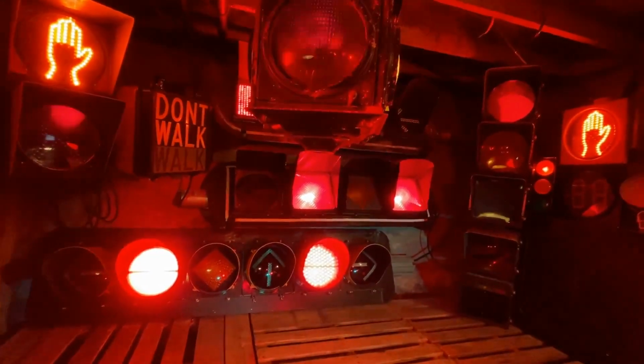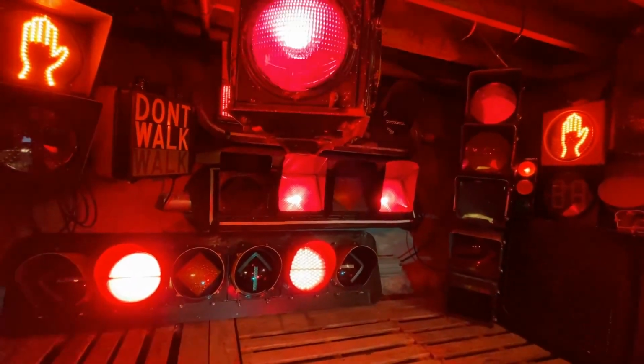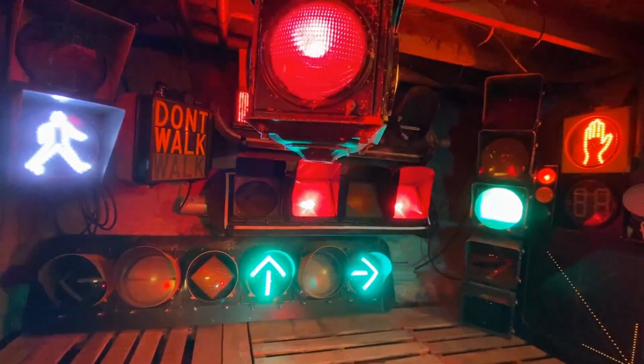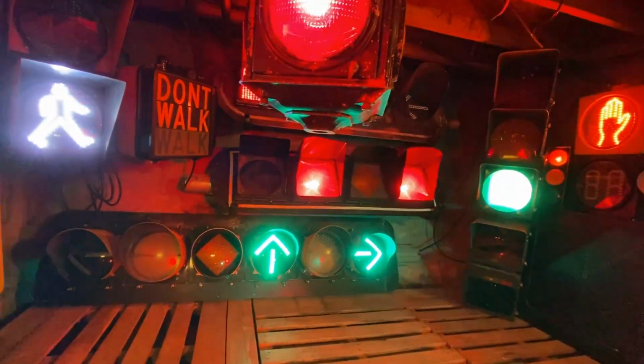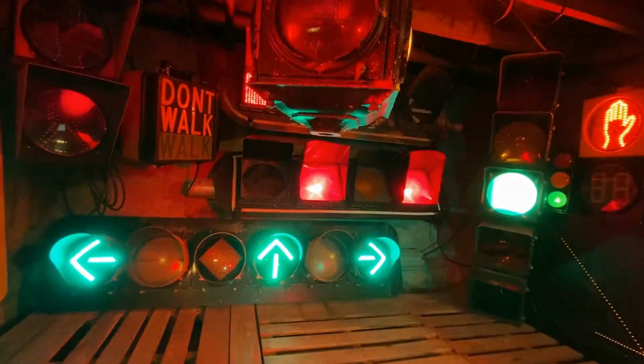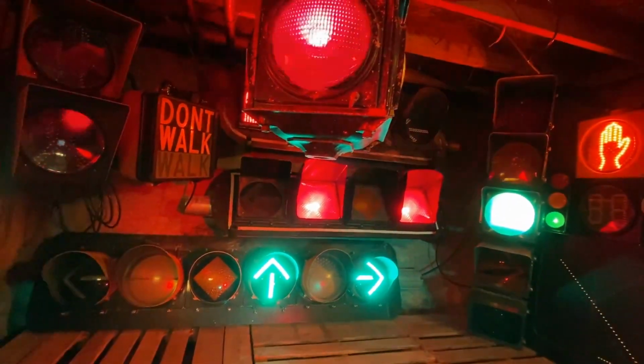And then I also have a logic statement currently set up that will always call up the pedestrian phase if phase 9 is on, which is the exclusive pedestrian phase. And then it runs an LPI.